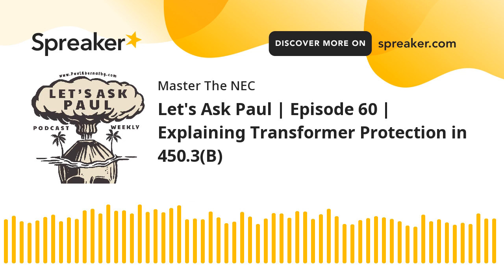So in your code book, if you go to the actual code language in 450.3(B), it's very short, very sweet. It says overcurrent protection shall be provided in accordance with Table 450.3(B). This is dealing with transformers rated 1,000 volts nominal or less, which is probably the lion's share of what you folks are going to be working with, right? It's a whole different table if you're dealing with over 1,000 volts. It works the same way, but it's a little more tedious in how you look at the table. We're going to focus on 1,000 volts nominal or less, because the question that was submitted referenced 450.3(B), and that obviously deals with 1,000 volts or less. So we're going to jump down to the table and give you the lay of the land.